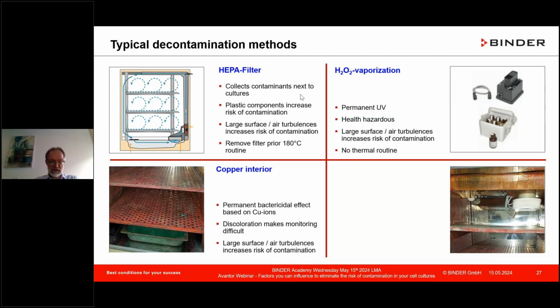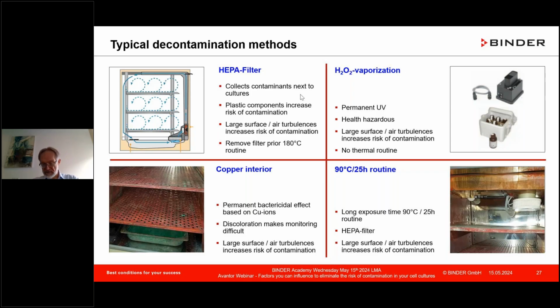That's an aesthetic thing. Discolorization. That I found out that is more a philosophy issue. That's like if you drive gear shift or automatic with your vehicle, both work, but it has its consequences like discolorization. Very, very difficult once you have a crumbly surface to detect spills, and that does not promote good contamination prevention. And then you have other routines other than that 180, which many CO2 manufacturers offer standard. You have 90° C, 25 hours, which is very, very long, more than twice as long as with 180. So it's overnight at least. You're wasting a lot of time there.